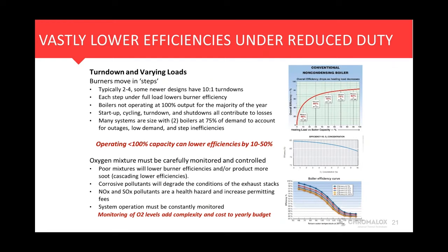You have to factor in startups, turndowns, and shutdowns, which all contribute to losses, such that a lot of times with these fuel-fired systems you actually use 2 boilers at reduced capacity, one operating at full while the other throttles. That factors in additional capital cost, since now you have 2 boiler systems to maintain, and you're still looking at operational efficiencies being decreased with all these changes in demand.